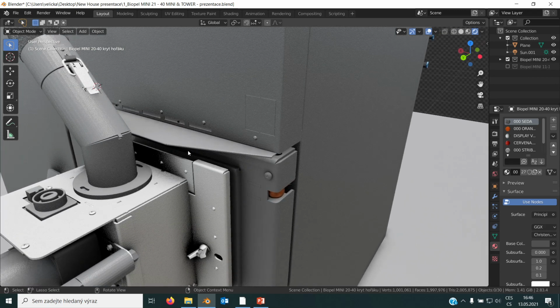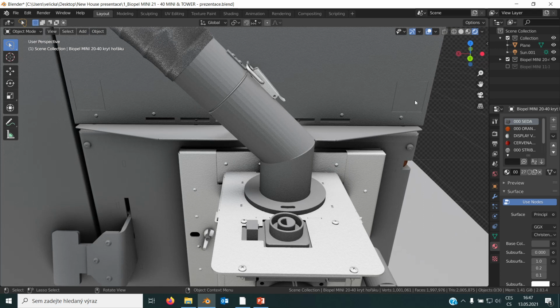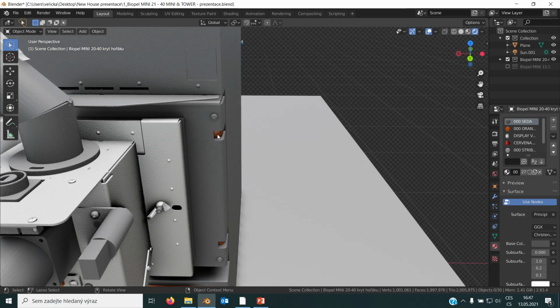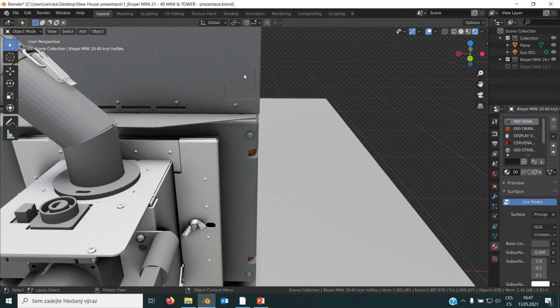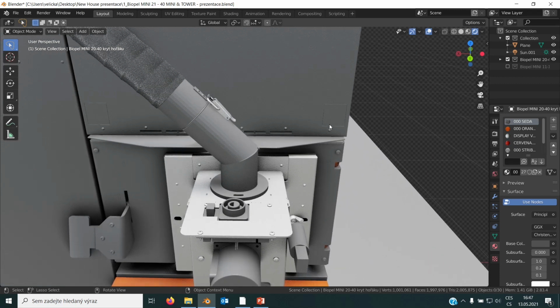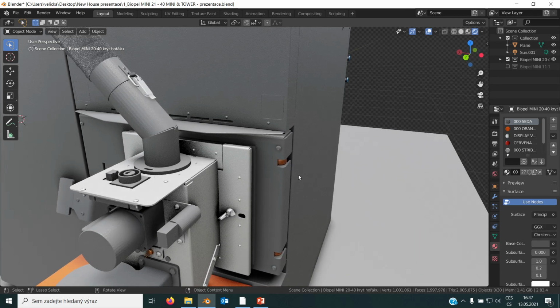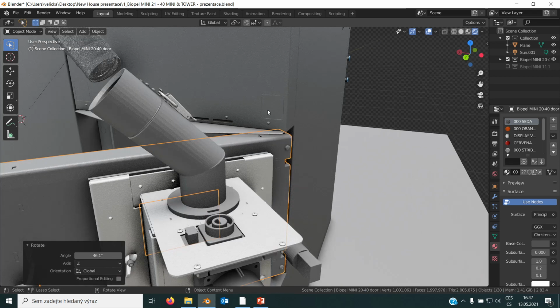And again, it's up to you to decide on which side the burner cable will be installed. So again, from the factory, the hinges are on the right side, so the cable for the burner should be moved through this opening where the hinges are. As you can see, both openings are covered from the factory, and it's up to you to open the correct hole for the burner cable, and it depends on the hinges. So when the doors are opened to the right side like this, you will choose the right opening for the cable to connect it to the burner.